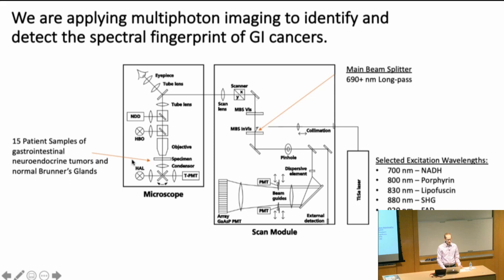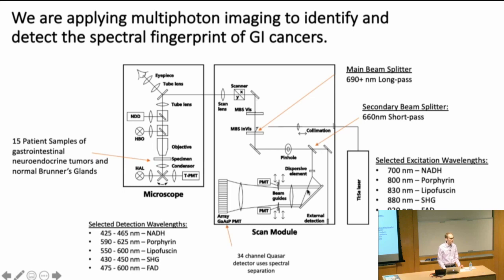Then, of course, on the return, it travels back through, passes through the beam splitter, because now that the frequency has been doubled, it no longer gets hit by that long pass filter, or rather, it gets redirected by the long pass filter. It goes through a secondary beam splitter, and it goes into this really nice detector that you can vary different spectral channels for detection. And so essentially, it has a series of diffraction gratings that you can rotate at different angles to let yourself capture really whatever spectral range you want on the return light. And so we are detecting specific wavelength bands for each of these biomarkers as well.